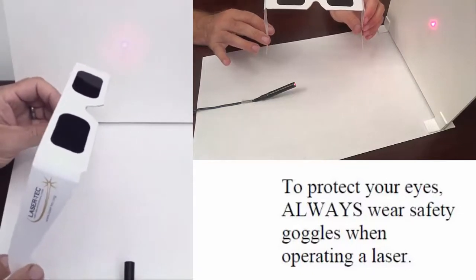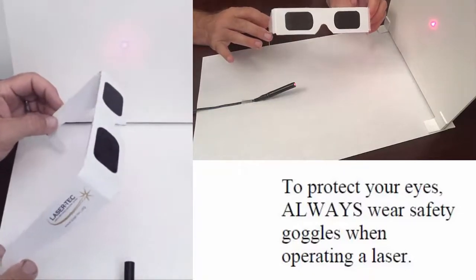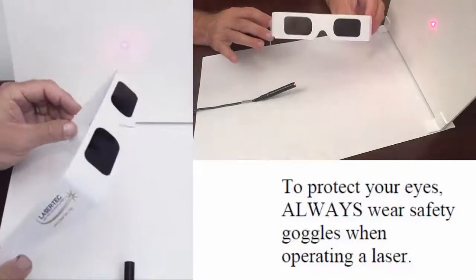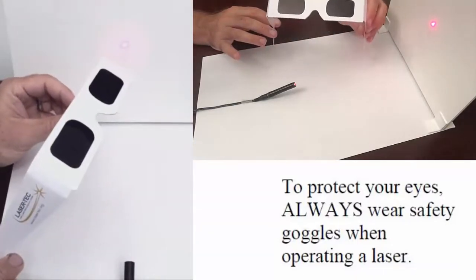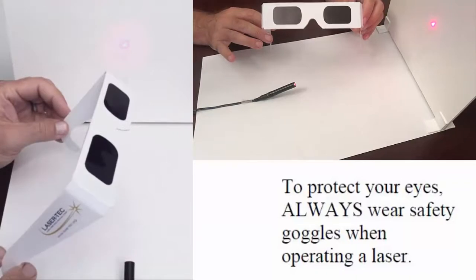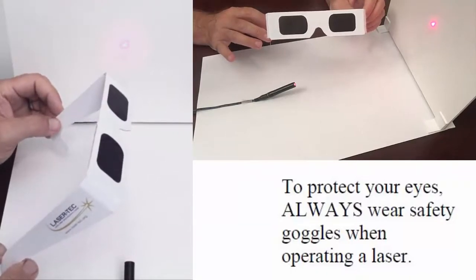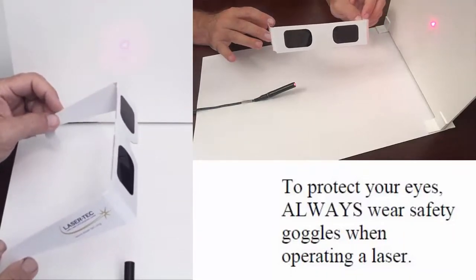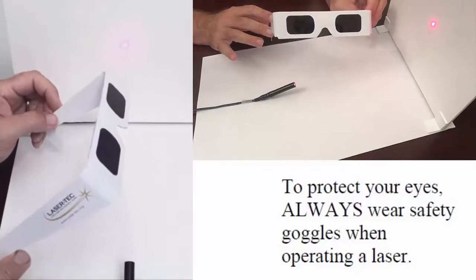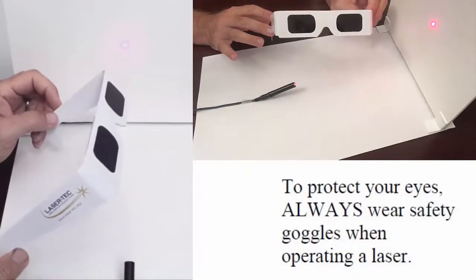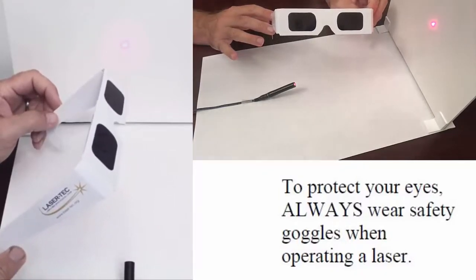Laser safety eyewear represents personal protective equipment. Here we have a simple laser safety eyewear that's part of your kit. Every laser safety eyewear is used for specific wavelengths and has a specific property, so-called optical density, that gives information about the ability of the eyewear to block or filter the light coming out of the laser.